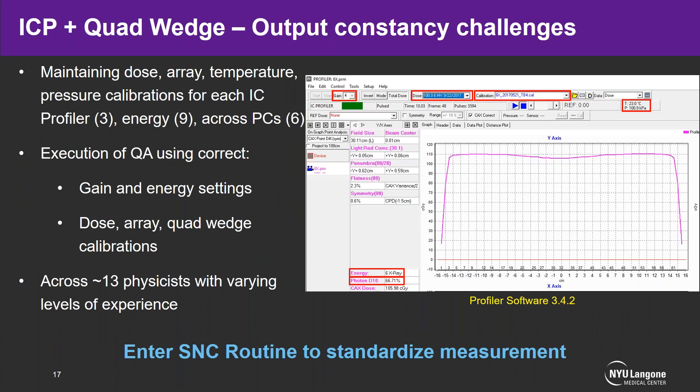Overall, the quad wedges proved to be excellent devices for energy constancy, removing much of the variation from the Farmer chamber in water setup. The next question was whether we could use the IC Profiler and quad wedge for output constancy checks. We ran into issues because we would need to maintain dose, array, and temperature-and-pressure calibrations for each of our three IC Profilers across nine energies and across PCs. Energy checks also require energy- and machine-specific array and dose calibrations, and gain settings must be correct for higher dose rate beams like triple-F modes.